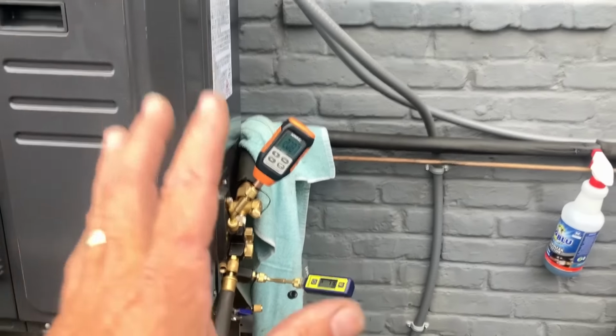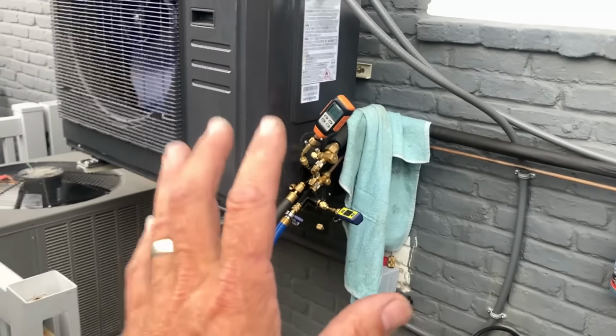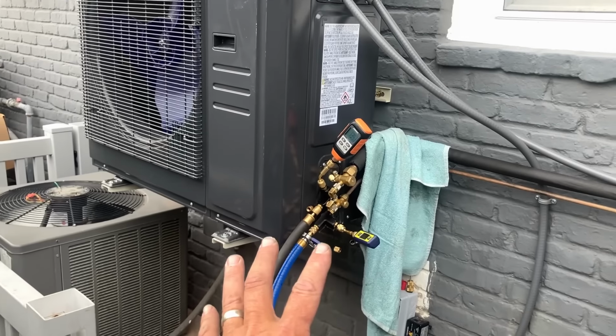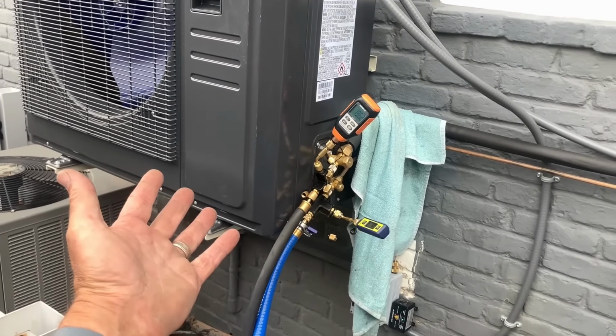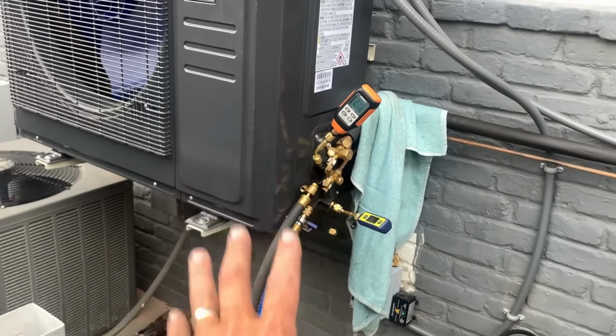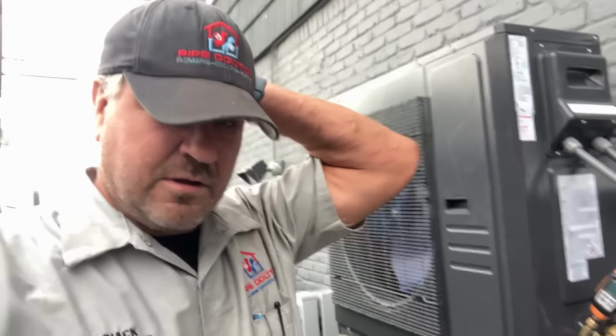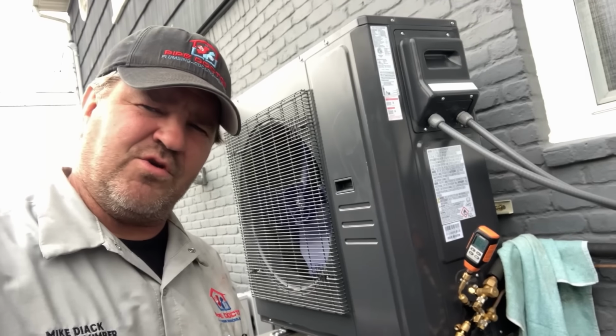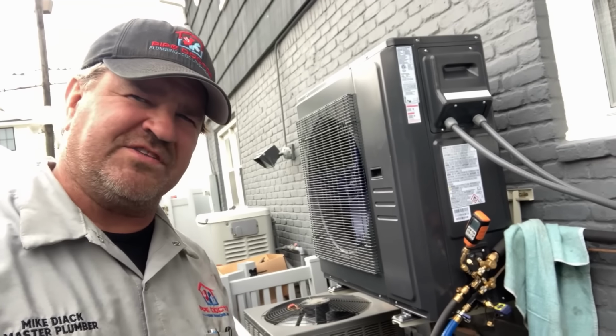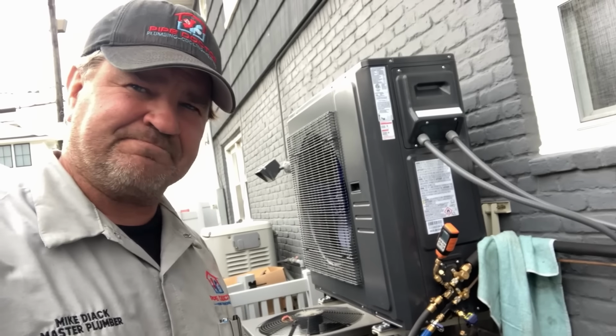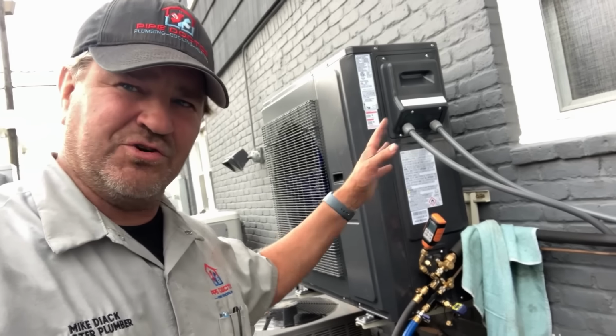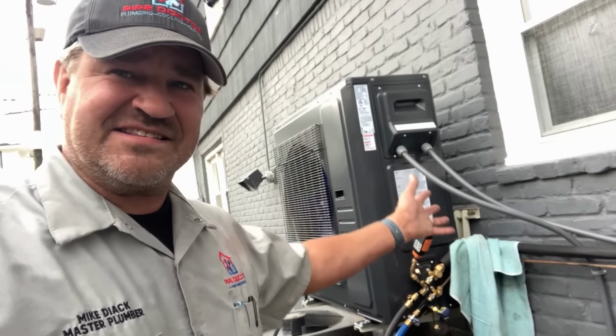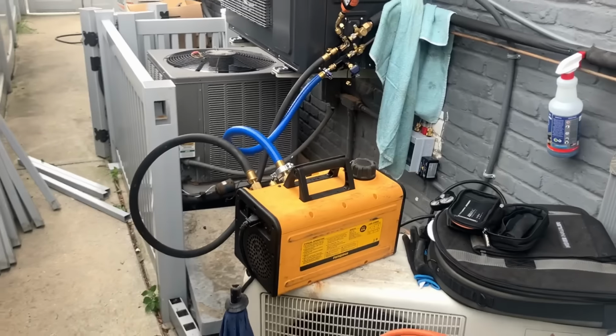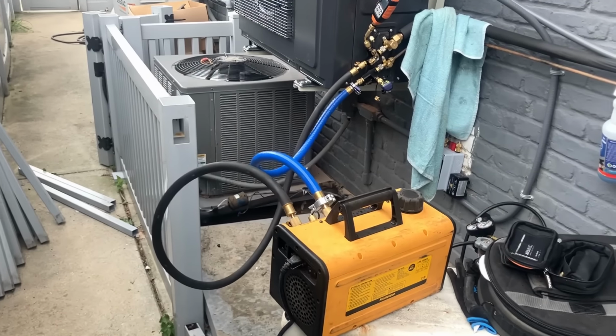This is the most crucial part - I say this over and over again. This is the most important part in any kind of refrigeration system, whether commercial, industrial, ductless, or ducted unitary equipment like a central air system. If you ask me what the single most important step is when installing a new air conditioning or heat pump system, it's not the way you hang the equipment or make it look pretty, it's not running the line set, it's not about making pretty ductwork. It's about pulling a proper deep vacuum. And this is the part that separates an installer from a mechanic. Here's why.